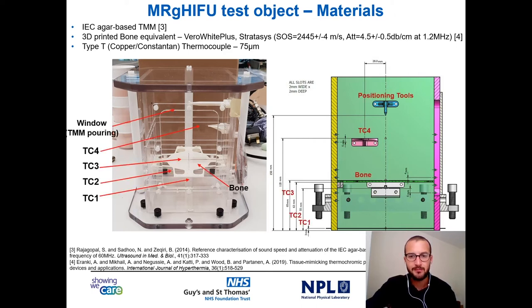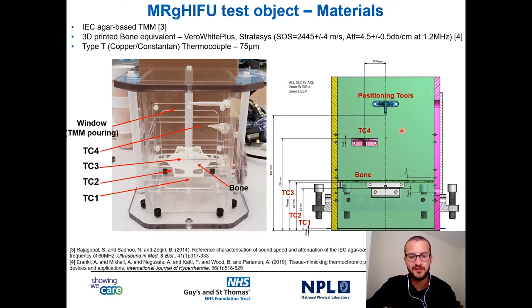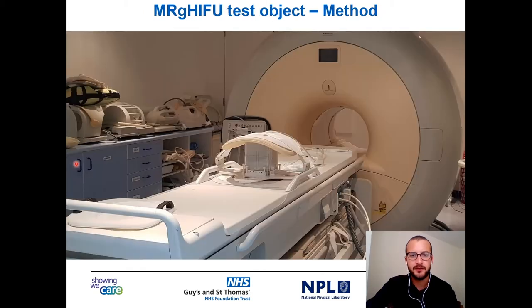Thermocouples were placed in the region below the bone and above the bone, and one thermocouple was used as reference. Positioning tools and engravings were manufactured for supporting thermocouple identification in 3D space in magnetic resonance imaging. Here you can see the setup of the phantom on the Sonalleve. This is the HIFU table, this is the phantom, and this is the MRI coil.